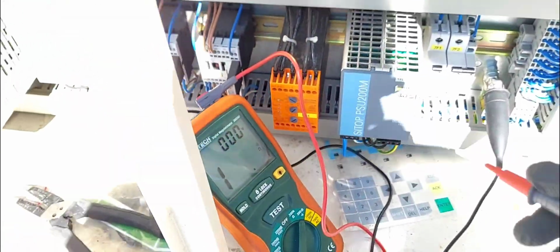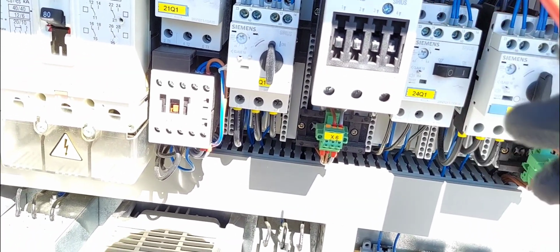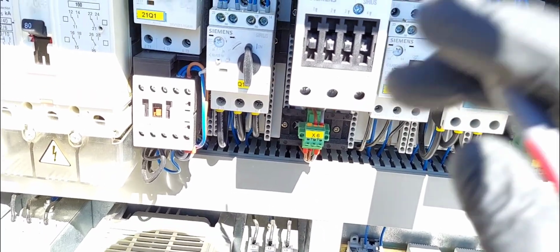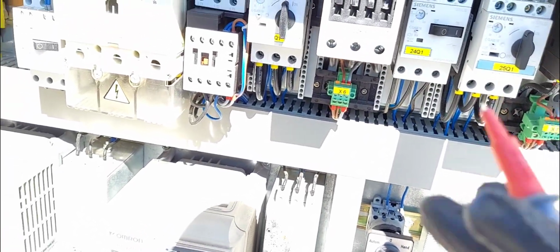Let's get into testing. Initially, what you're going to want to do is make sure the power is off to the device you're testing, the compressor motor windings. Now in this particular scenario, it's a medical chiller. I cannot shut down the power to the entire unit. However, that is recommended. As a pro, sometimes you have to do work on the system while it's live, because for the system to be completely down, an appointment has to be made, scheduling, etc. It's a lot involved. So I'm careful, I know what I'm doing. I can do it while it's live.